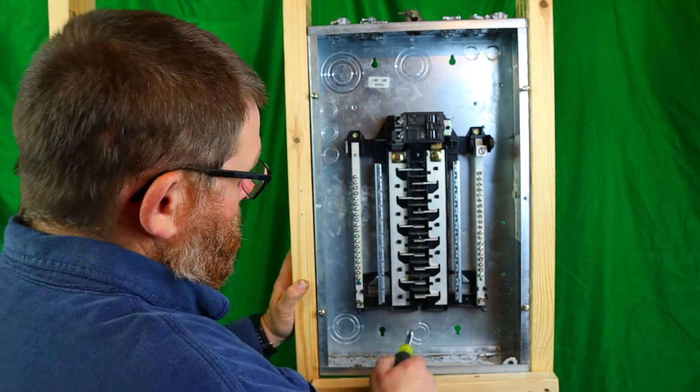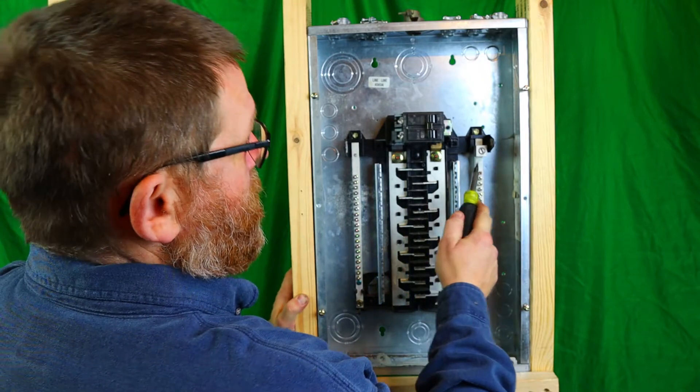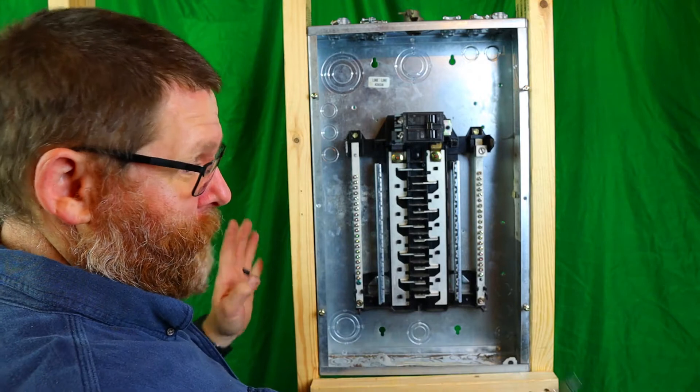...this ground bar right here to this can of this panel, it will beep - your meter will beep. If you do it from here to here, it will not. So that way you know for sure. I'm going to show you here in a second.